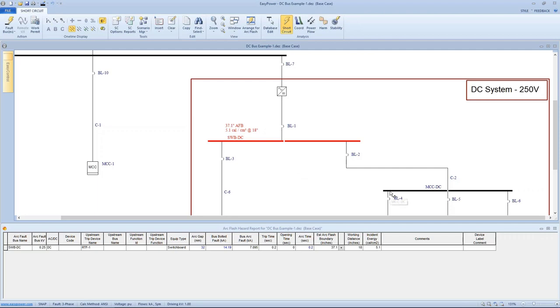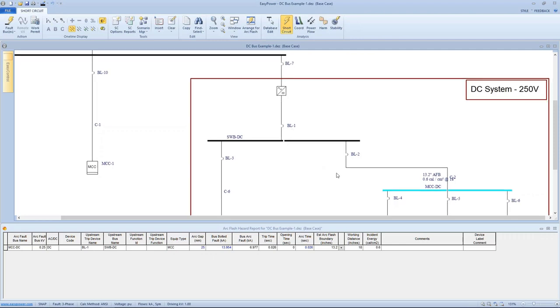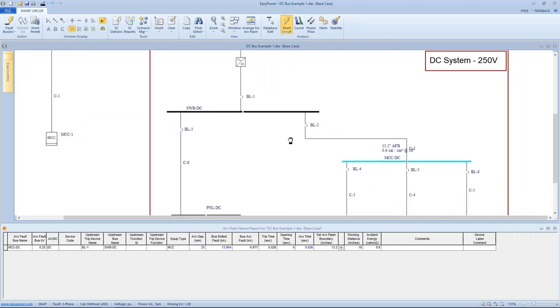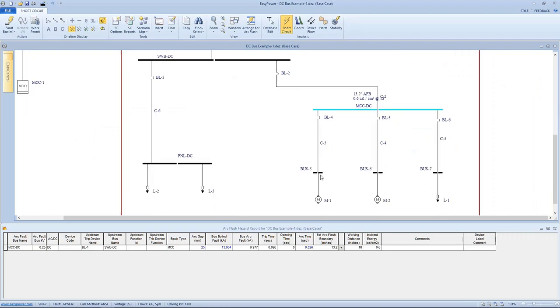If we were to fault this bus, we'd see that we have an upstream device BL1, which is actually providing the protective devices. The question arises, why doesn't BL2 get into the mix? And that lends more or factors more into the conversation about the difficulty in trying to do coordination for low voltage systems. And so we're going to touch on that briefly, but we'll talk more about it in a couple of weeks.